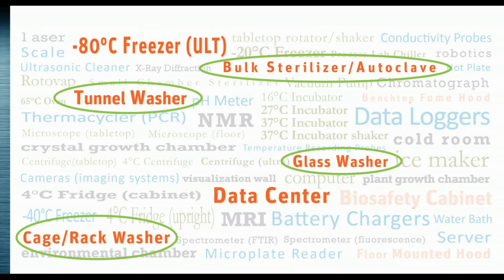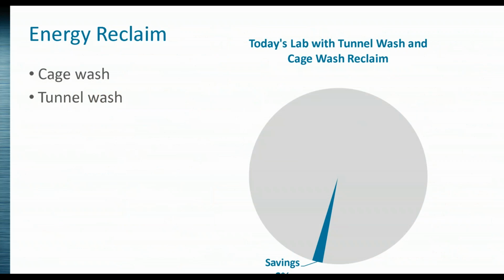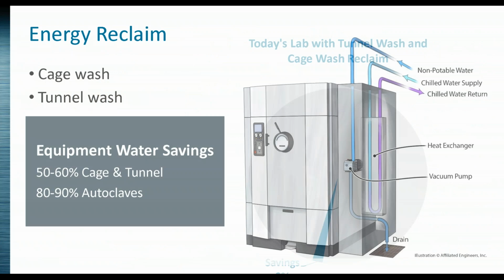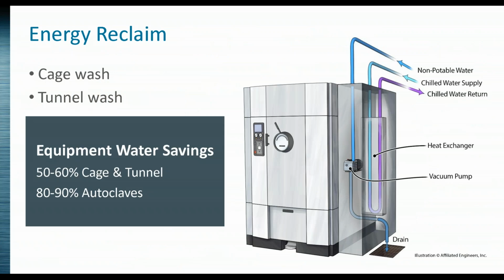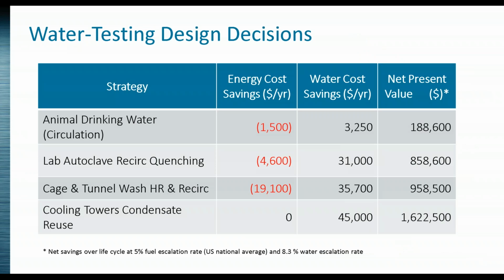Now, the last piece I want to talk about is process equipment that lab planners tend to have more influence over. We're seeing opportunities with cage wash and tunnel wash, where we've got reclaim in many cases by using chilled water heat exchangers instead of dumping potable water down the drain to quench these units. There's a significant amount of water that can be saved, so we have both energy and water opportunities with this lab equipment.